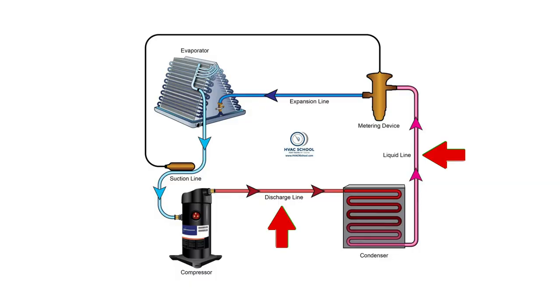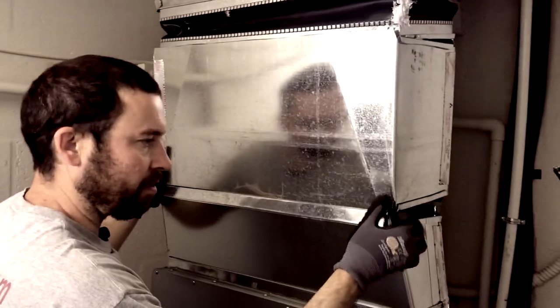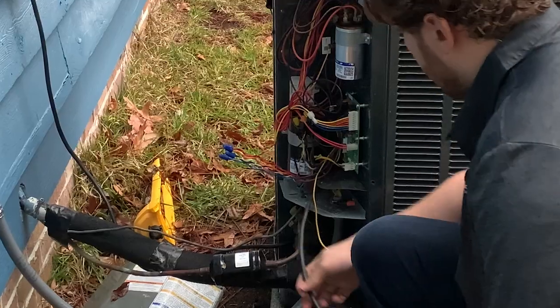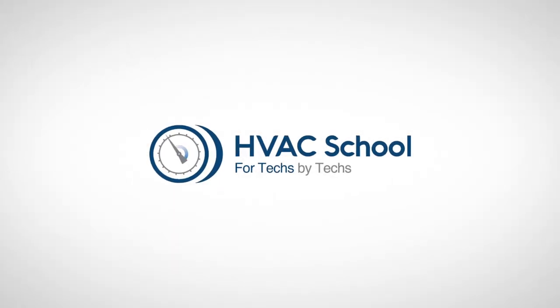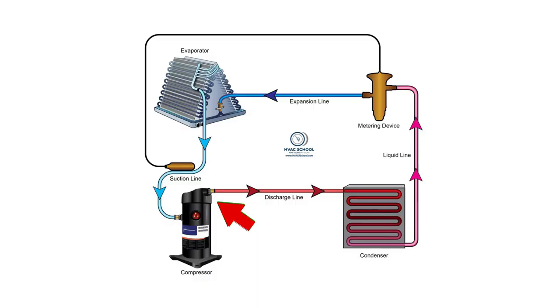Thanks for watching this quick video. We're talking about liquid lines and discharge lines, some of the differences and things to know when you are measuring pressures and temperatures on both. Your discharge line is the line that leaves your compressor and goes into your condenser. It is a high pressure, high temperature vapor.